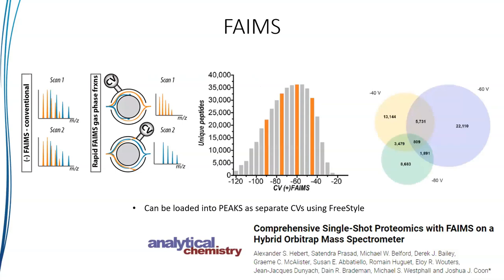First, I'd like to talk about FAIMS. This is the brand of ion mobility provided by Thermo, and it's quite different from other ion mobility variations. What they use is something called compensation voltage, where they switch between different voltages to pick up different types of peptides based on their ion mobility. With one compensation voltage they're picking up the orange peptides, and with another compensation voltage they're picking up the blue peptides, which in a traditional mass spec experiment would overlap in terms of their M/Z, and you wouldn't be able to get MS2 scans from each of them.